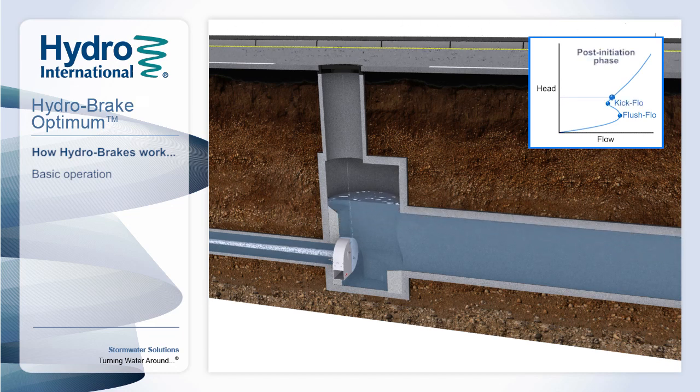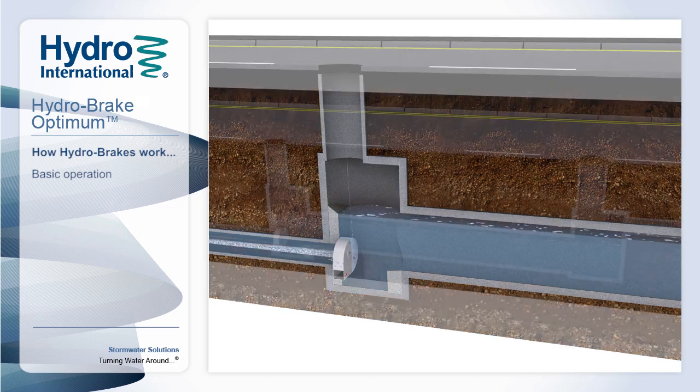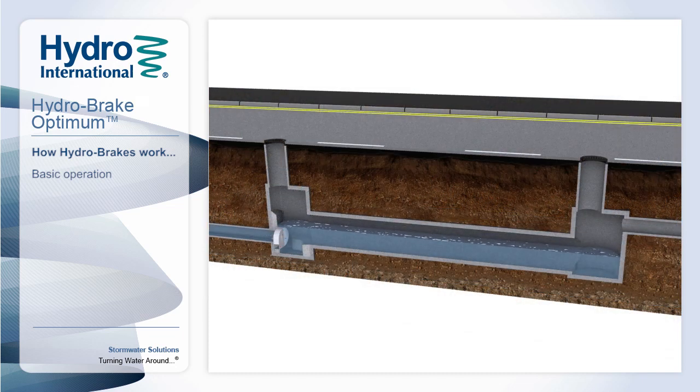We then enter the post-initiation phase, where the centre of the outlet is filled with air, which effectively chokes the flow through the unit, restricting it to the design flow. This phase continues until we reach the primary design point. As the water level subsides, the vortex collapses, and the Hydro-Brake Optimum returns to operating like a traditional orifice with a large aperture, ensuring that the drainage system is ready for subsequent rainfall events.